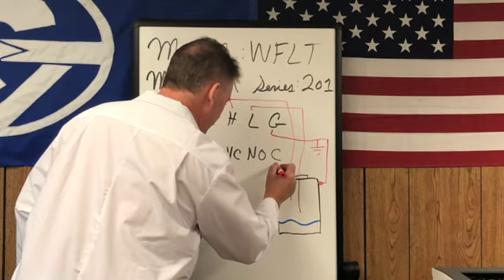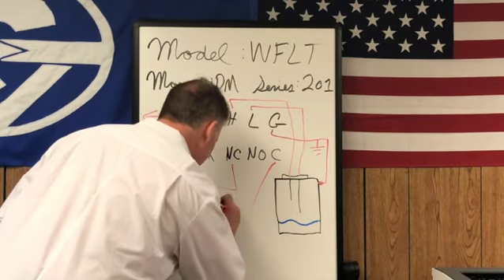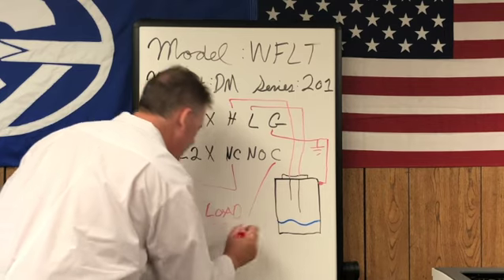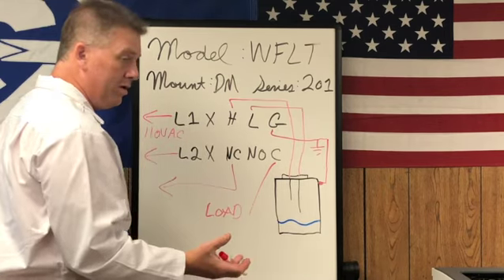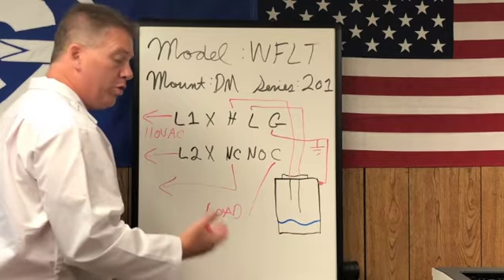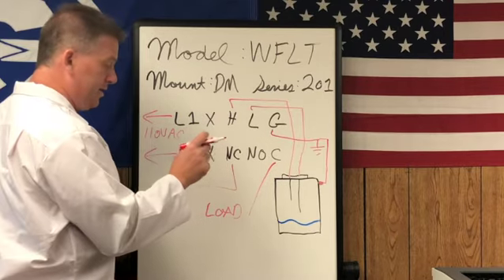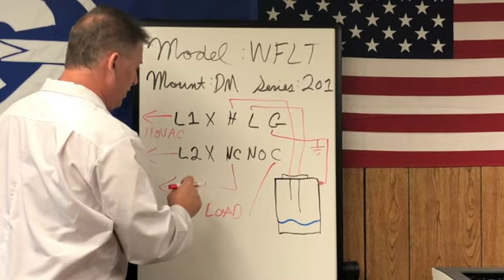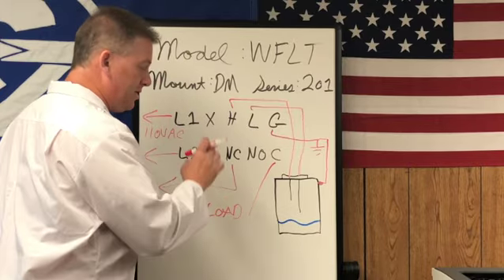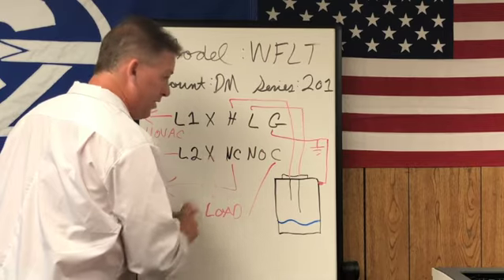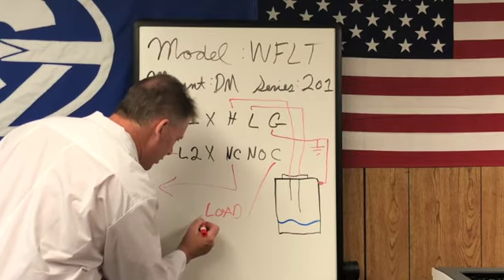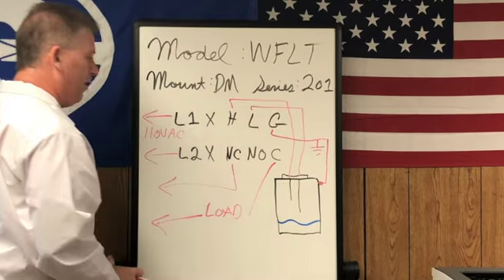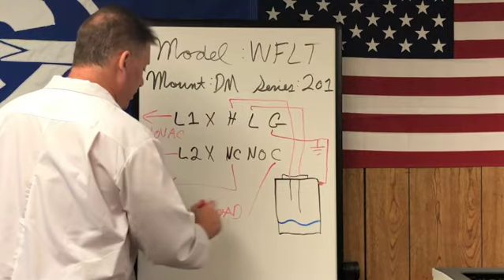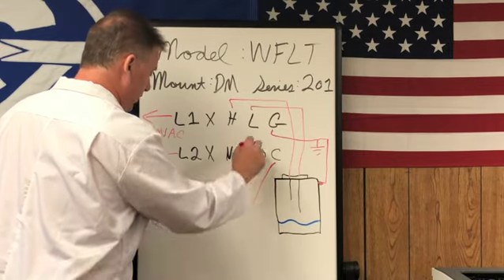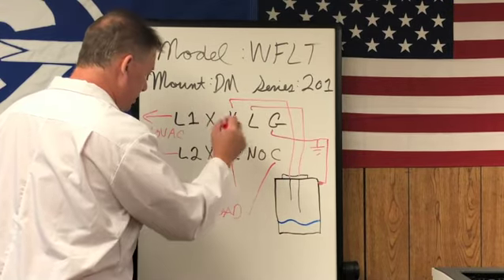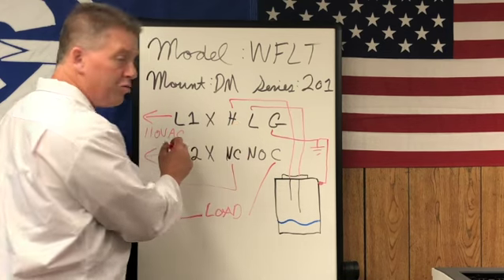Your common is going to come off the relay, and this is where you hook it up to your load. When I say load, I mean a pump, a contactor, a solenoid valve, anything that doesn't exceed that threshold, which on this one is 10 amps at 110 volts. As long as it doesn't exceed that, you're good to go. The load we're going to bring back to line power. You can use the same line power as long as it doesn't exceed the threshold of the relay and it's the same voltage. You can use the line power you've just brought in here for the unit.